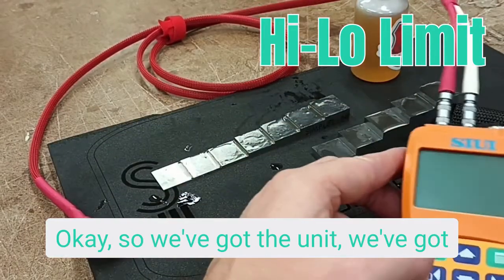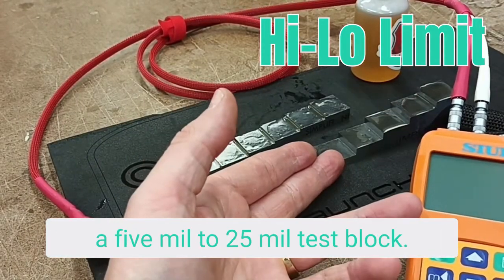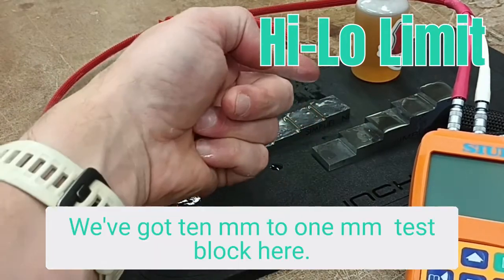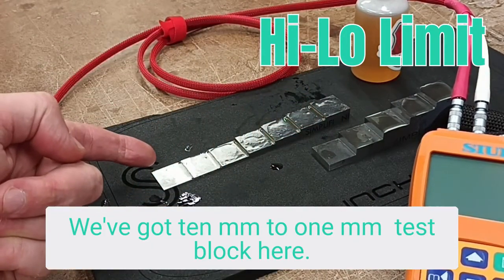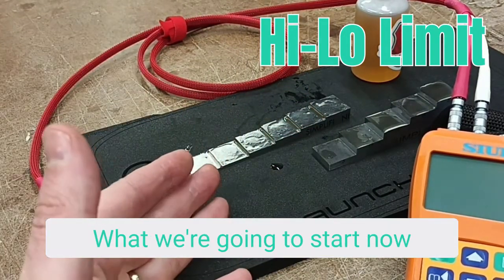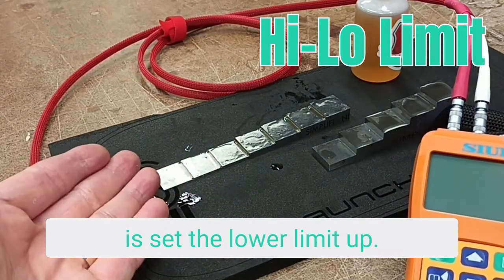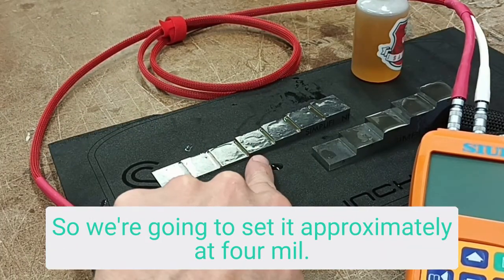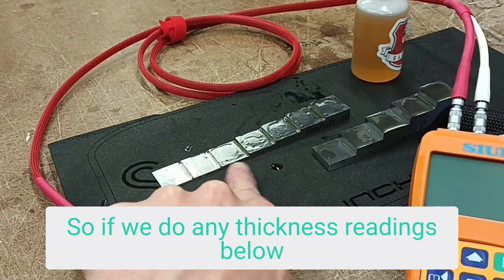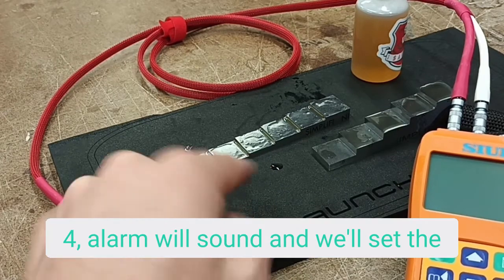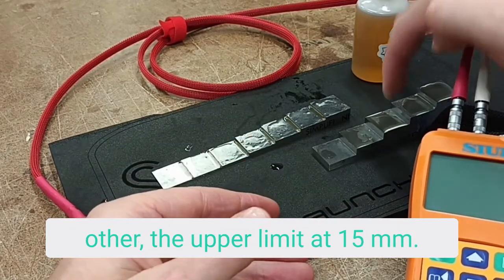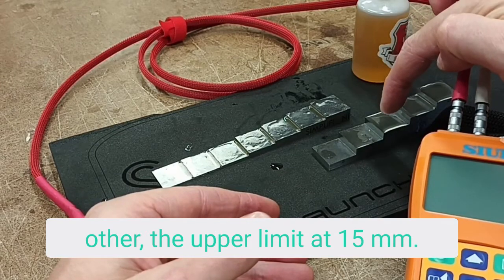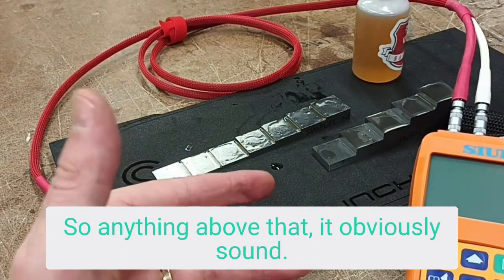Okay, so we've got the unit. We've got a 5mm to 25mm test block. We've got 10mm to 1mm test block here. What we're going to start now is set the lower limit up. So we're going to set it approximately at 4mm. So if we do any thickness readings below 4mm, the alarm will sound. And we'll set the upper limit at 15mm. So anything above that, it'll obviously sound.